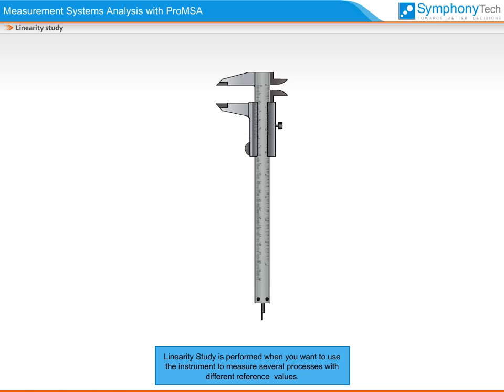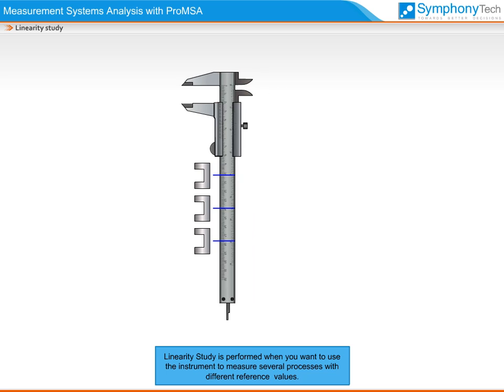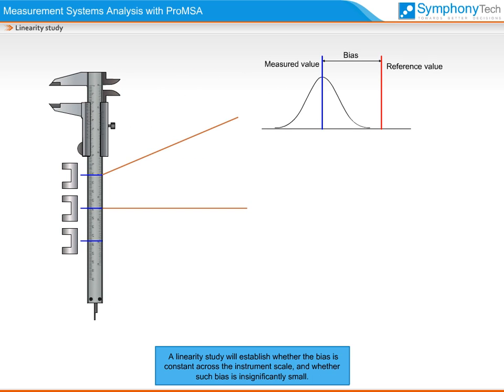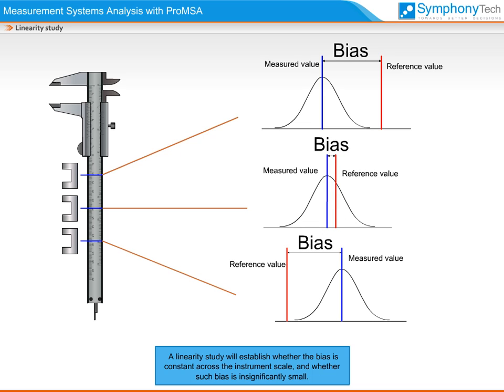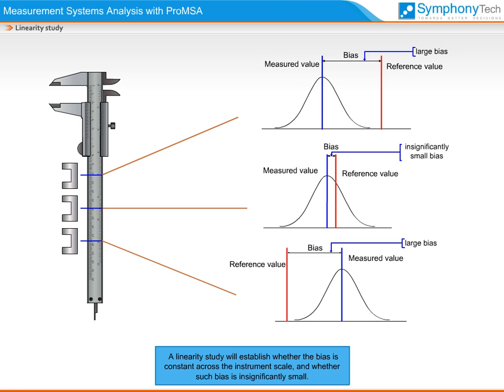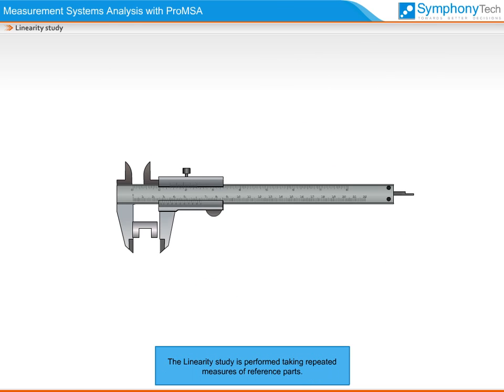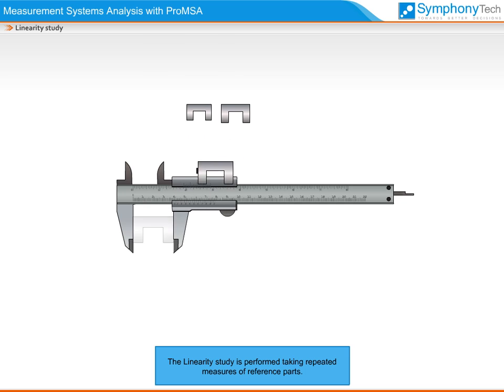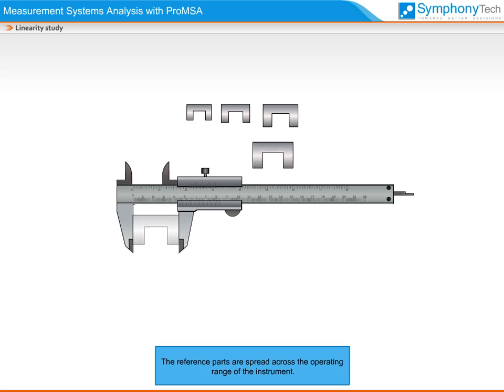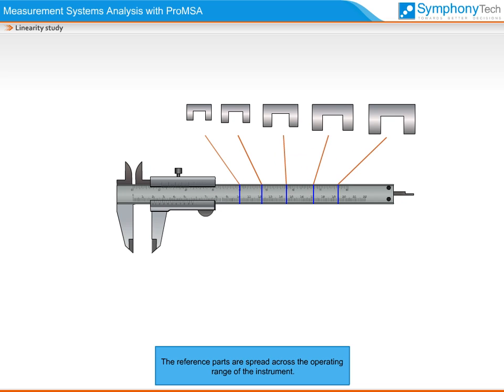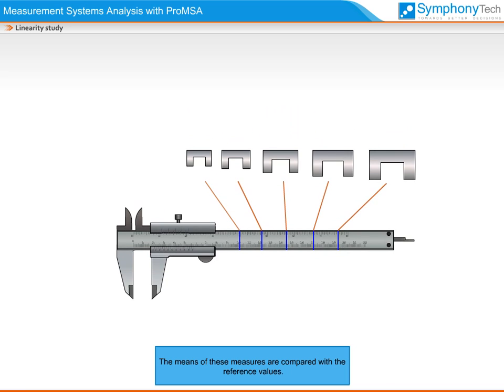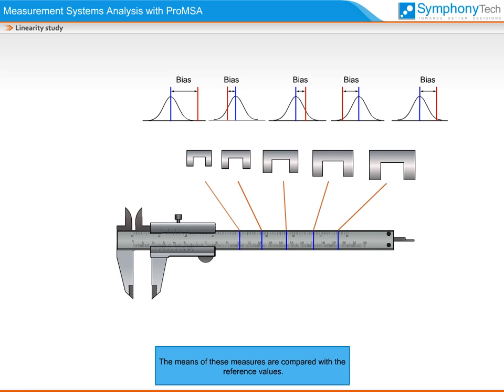The linearity study is performed when you want to use the instrument to measure several processes with different reference values. The linearity study will establish whether the bias is constant across the instrument scale and whether such bias is insignificantly small. The study is performed by taking repeated measures of reference parts that are spread across the operating range of the instrument, and the means of these measures are compared with the reference values.